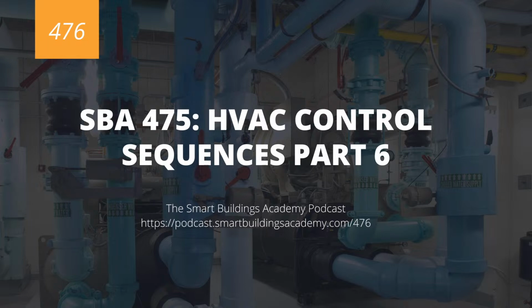Now, that is known as staging, and typically our stage parameters are somewhere like 90 to 95% load or full load amps, and you'll bring a second chiller on, and then 30% or less is your stage down. That's our typical settings. Now, we'll use these things called partial load chillers, which is typically a smaller tonnage chiller, to handle these loads below 30%.